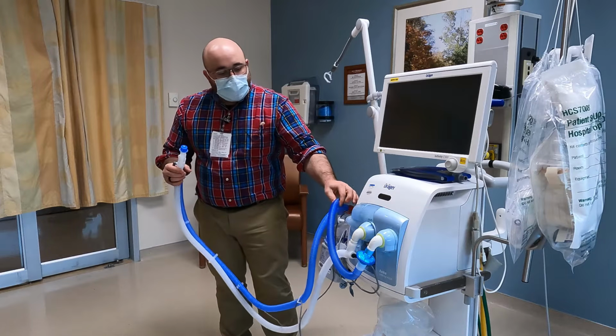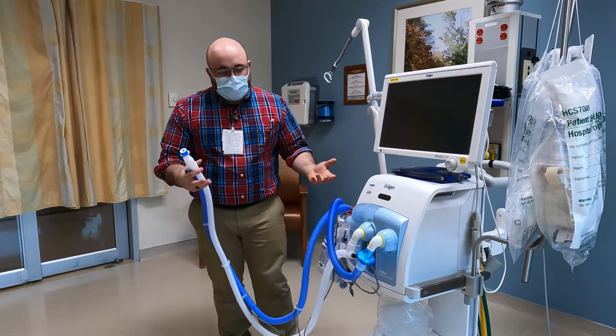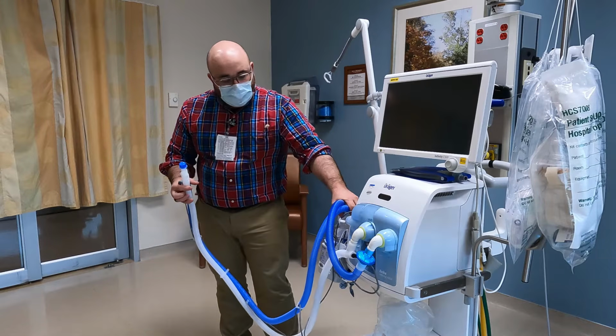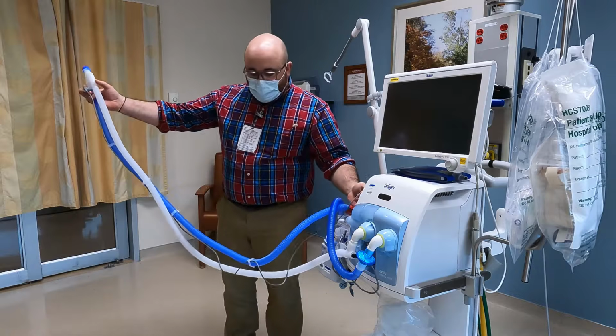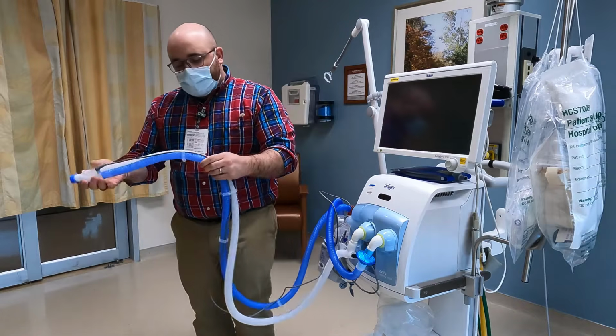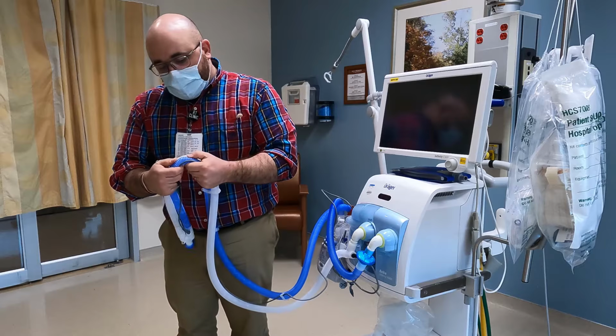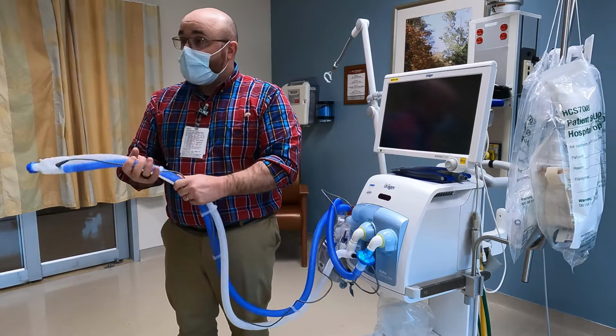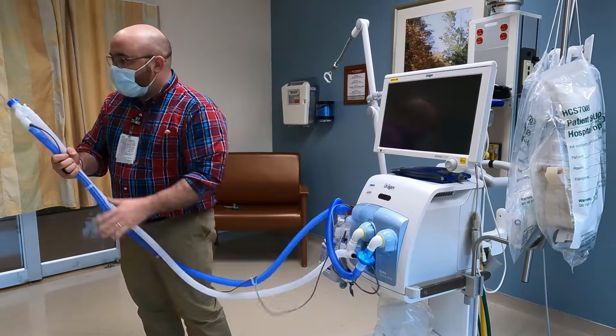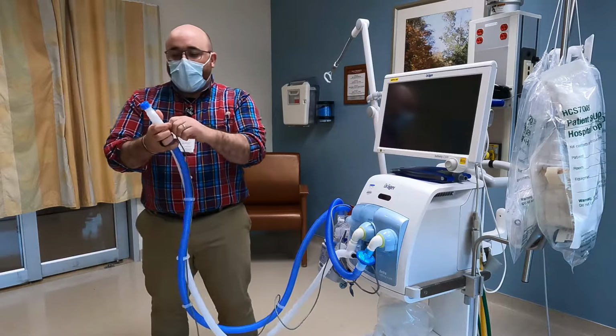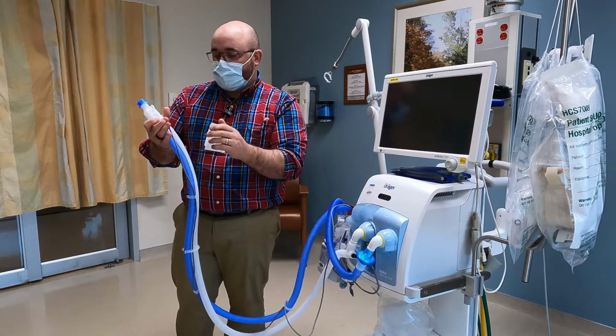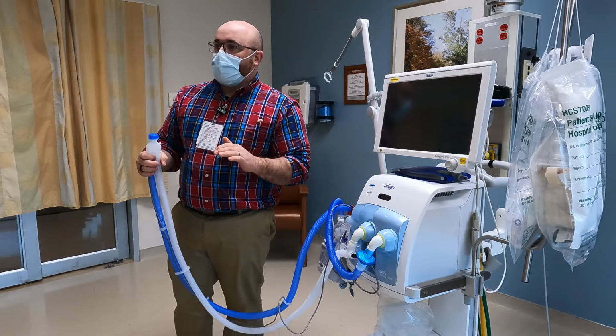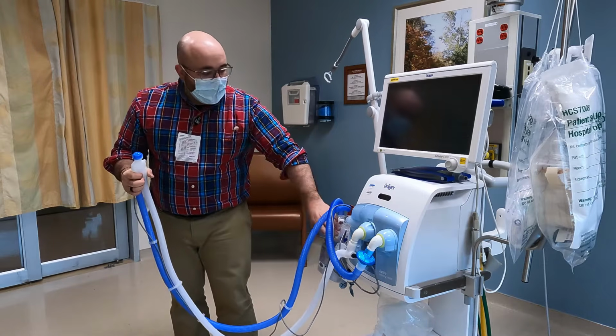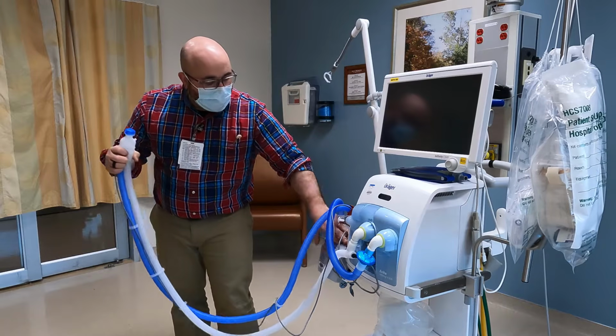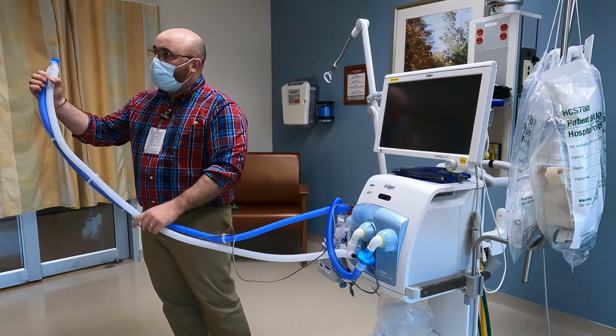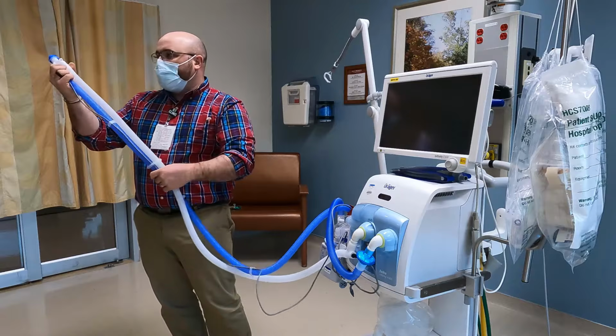So you always see the inspiratory limb. In this case, it's blue. I could flip these limbs and they would do the same thing, but in this case, it's blue. You also see a bunch of wires hooked up to it here. Inside of this circuit there are heater wires, and they warm it to 37 degrees so that it carries the moisture all the way out to the patient. If this wire stopped working for some reason, you are going to have a mass quantity of what we call rain out. So you're going to have 37 degree water, 100% saturated here, and it's going to come out here and start to cool. It's going to rain out. You get tons of fluid in the circuit.